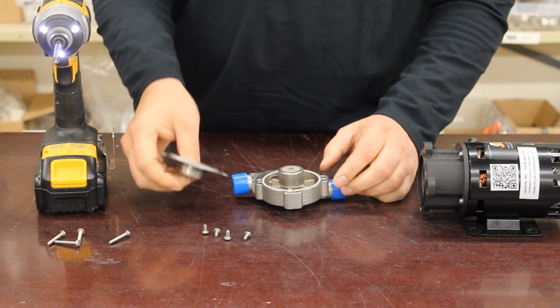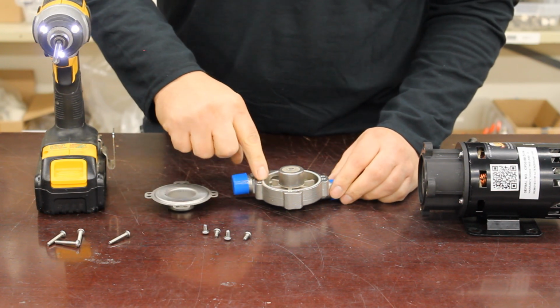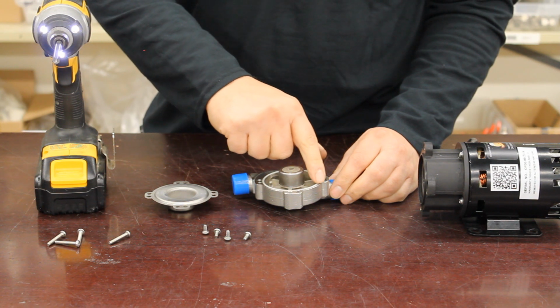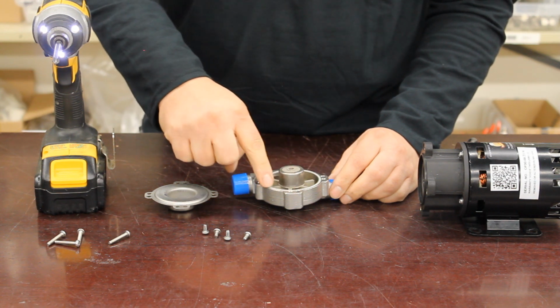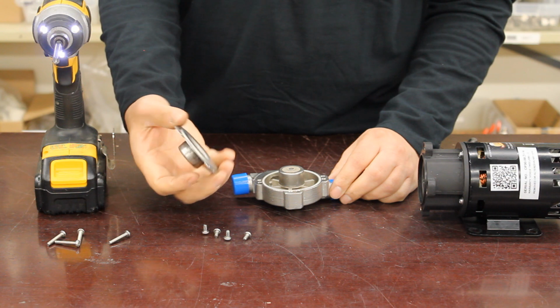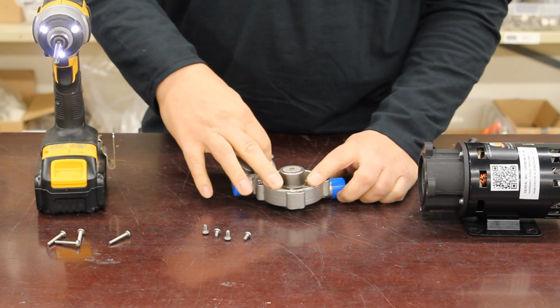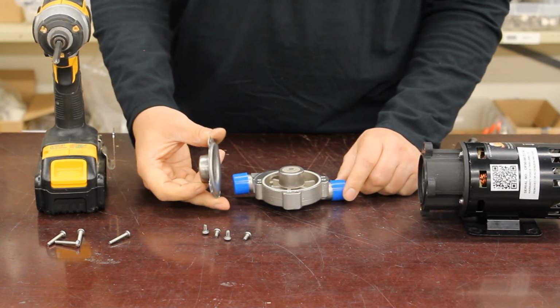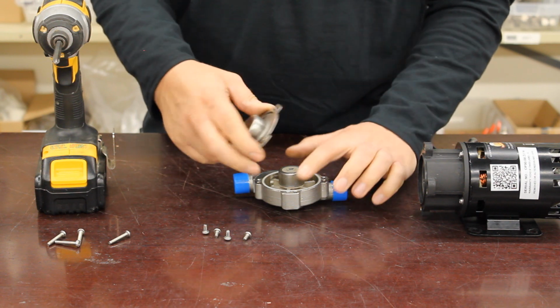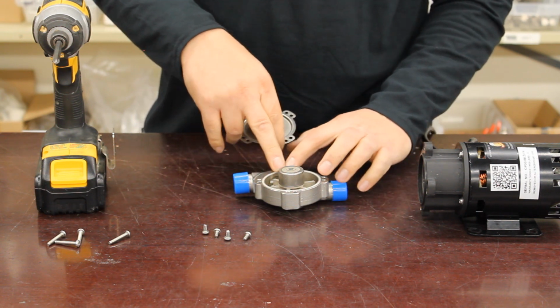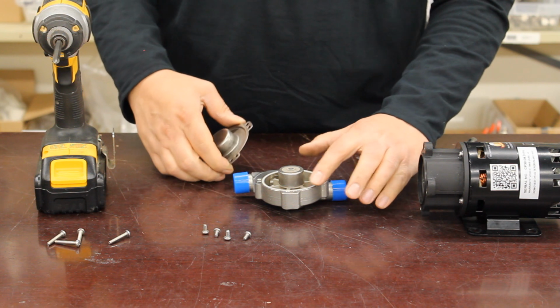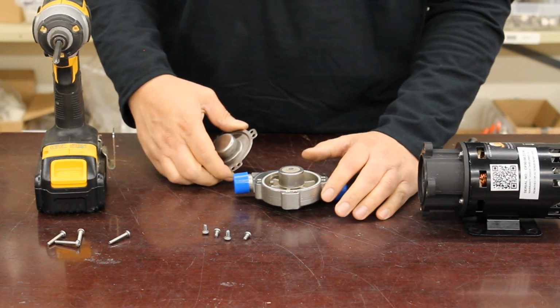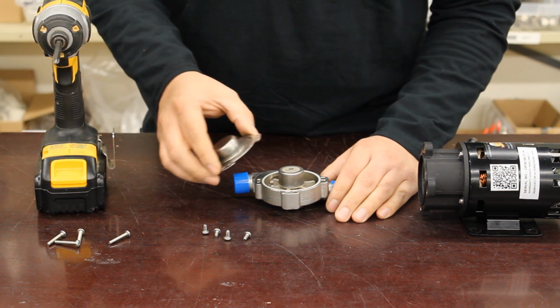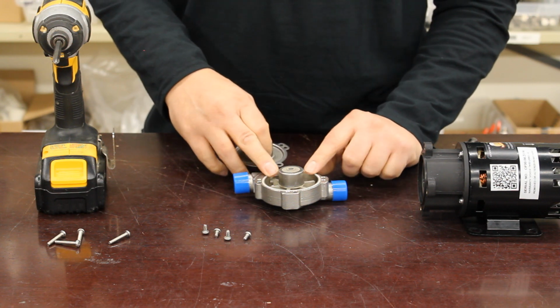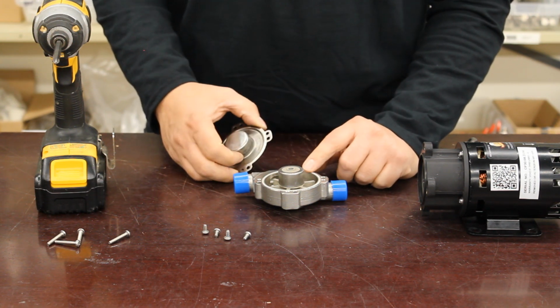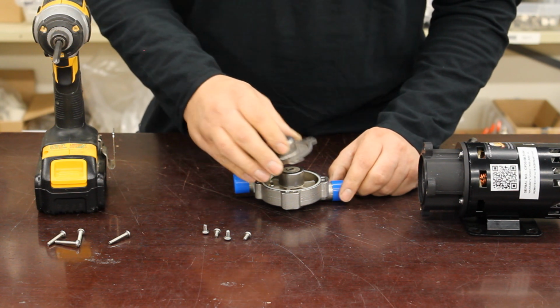All right, so here is the O-ring. It's a clear, thin O-ring that sits in a groove on the head, and when you screw the back cover plate on, it makes contact there. If you had any leaking issues, by the way, you would want to inspect this O-ring for tears or for any foreign material that might be laying across it, like hair or something like that, and perhaps just reseat the O-ring with a little bit of petroleum lubricant.